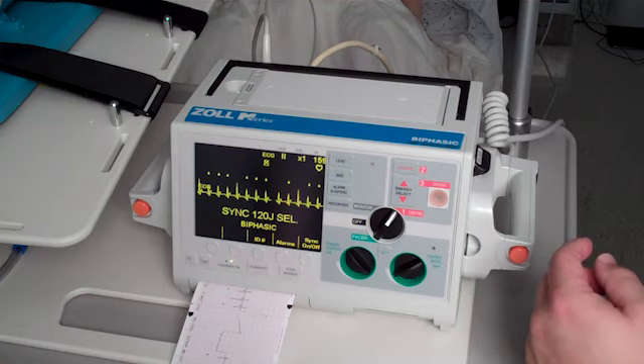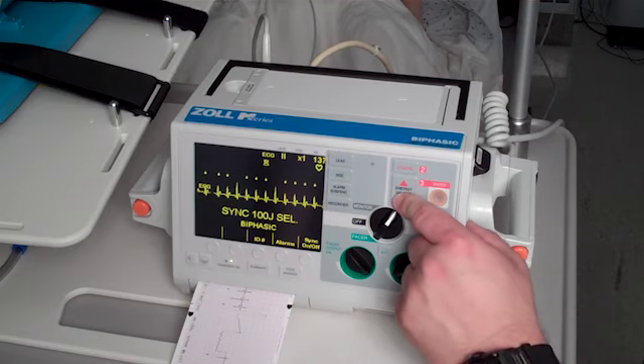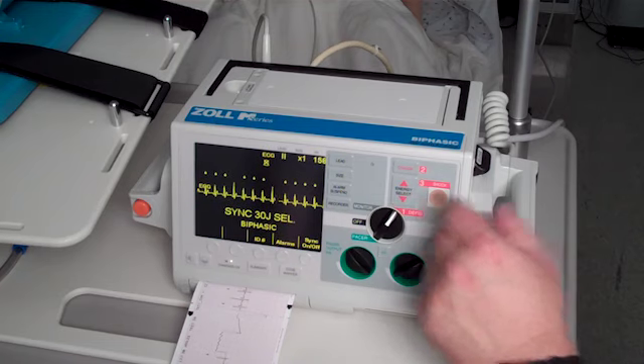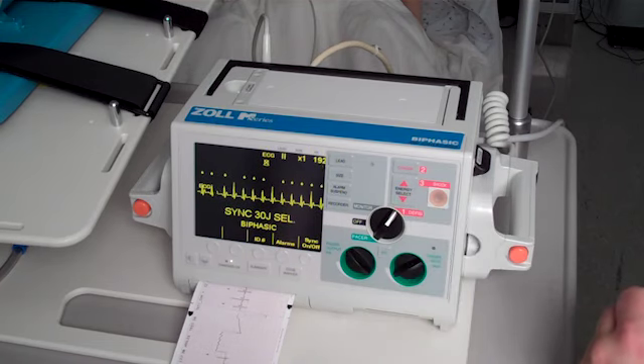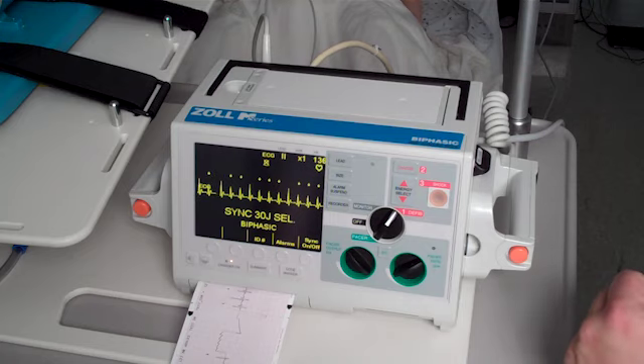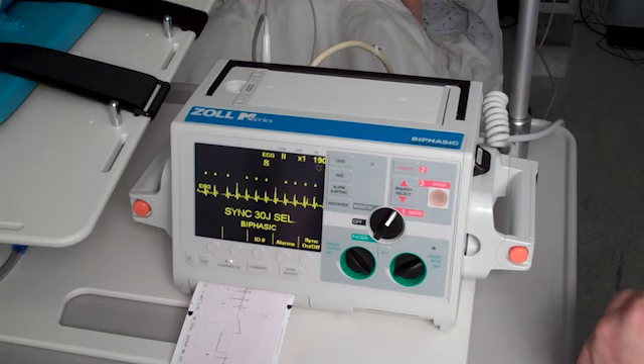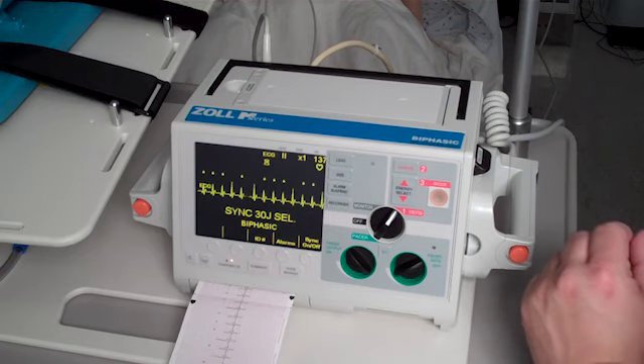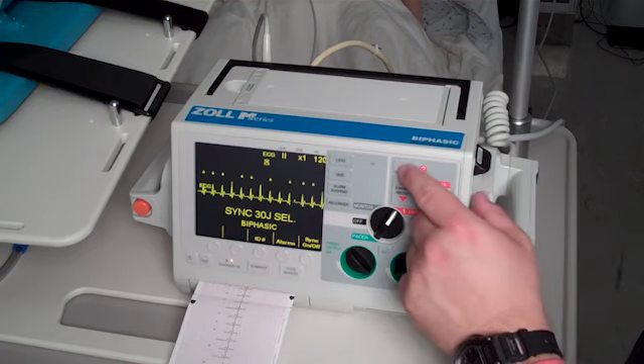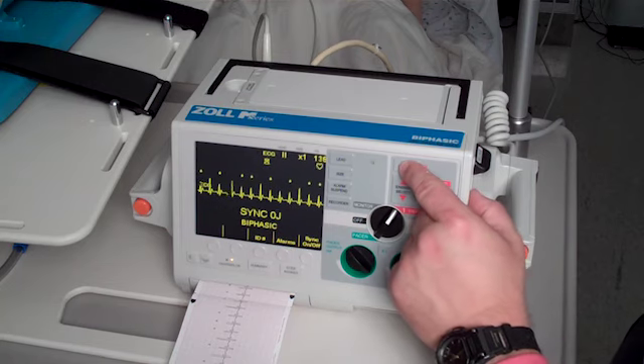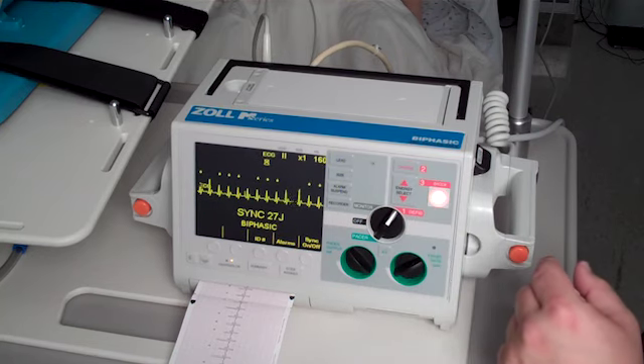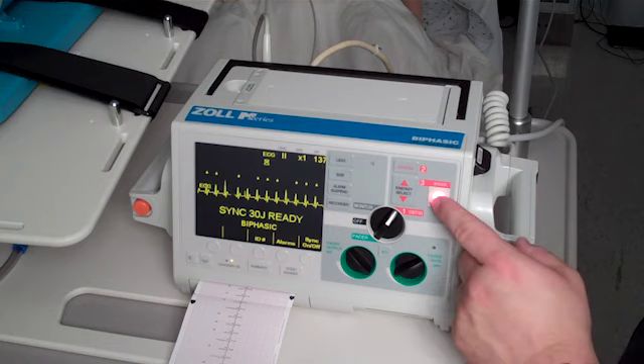Since cardioversion can be accomplished at a much lower energy setting than defibrillation, use the energy select button to lower the amount of energy applied during the shock. Administer adequate sedation to the patient. Once the patient is cleared of all personnel, press the charge button. Once the defibrillator is charged, clear the patient again and press and hold the shock button.